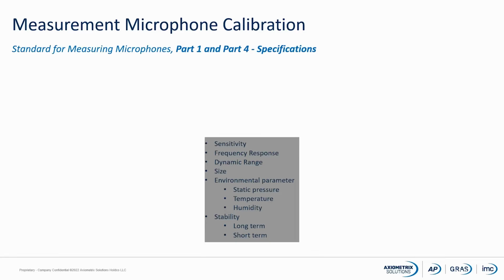If we have a closer look at part 1 and part 4 of the standard, actually the specifications, they look like each other. In the specification it's described that the microphone should have a certain sensitivity. The microphone, depending on size, should have a certain frequency response. The dynamic range is also described. The size of the microphone, the mechanical size, is described. Environmental parameters such as static pressure, temperature, and humidity are also described. The influence of these parameters is described in the standard.